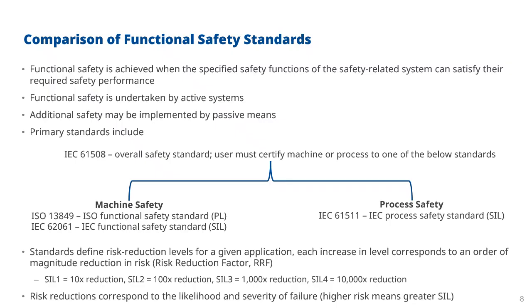But generally, if we have something like SIL 1, SIL 1 means that there are additional measures in place to reduce the probability of a dangerous situation by 10 times. If we go up to SIL 2, that's reduced by 100 times. If we go up to SIL 3, it's reduced by 1,000 times. And if ever you get to something like a SIL 4 system, now we're looking at a 10,000 times reduction. The idea is, these risk reductions correspond to the likelihood and severity of a failure. Higher risk means greater SIL and vice versa, although that's not always necessarily a good thing. Higher SIL does cost more money, and it might also lead to operational issues, including the simple fact of getting insurance for your application.